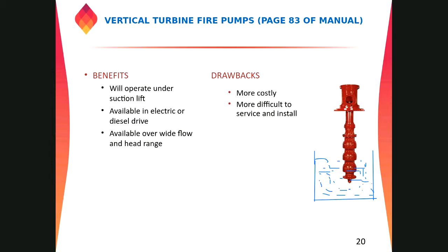But NFPA says that if water is coming to a pump from the suction side, at the suction gauge, the pressure shall not be below 0 psi. If the pressure goes below 0 psi, it means there is a negative suction condition, and maybe air will be trapped in the system, and it causes cavitation.